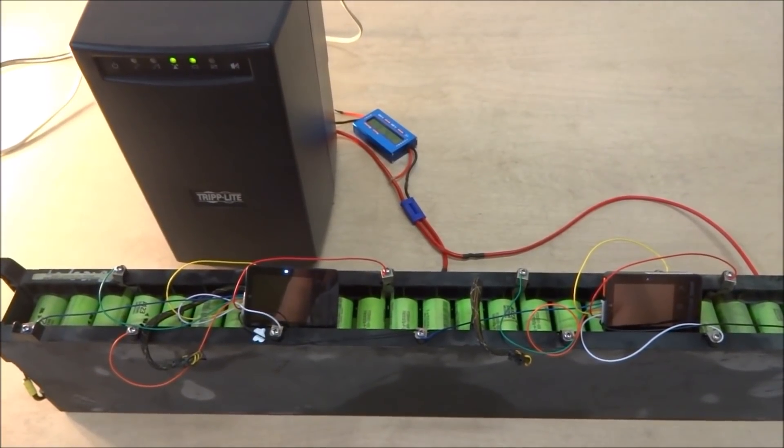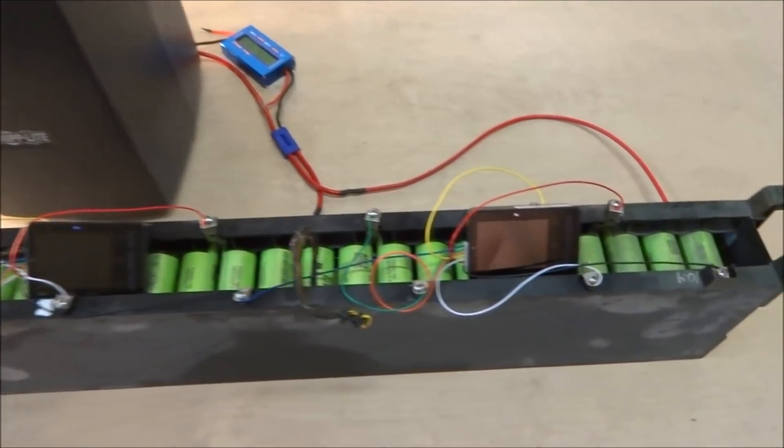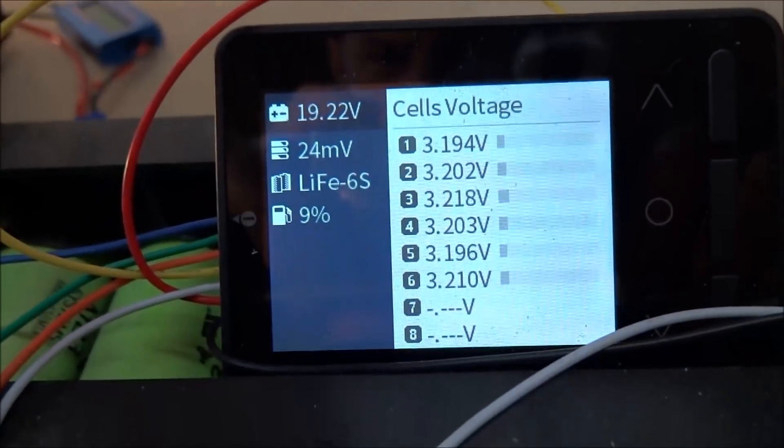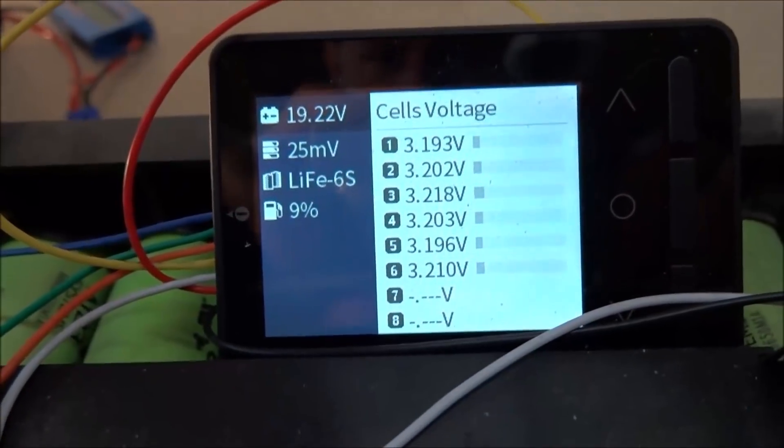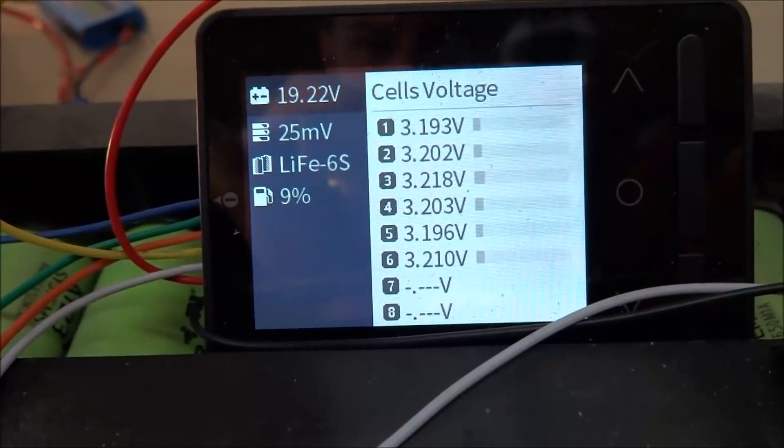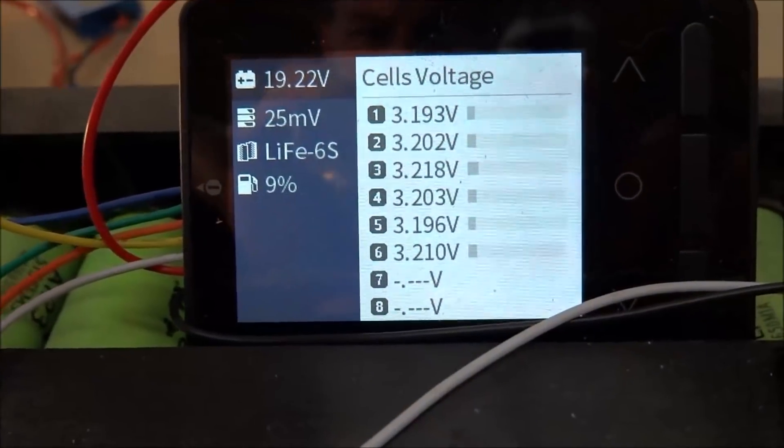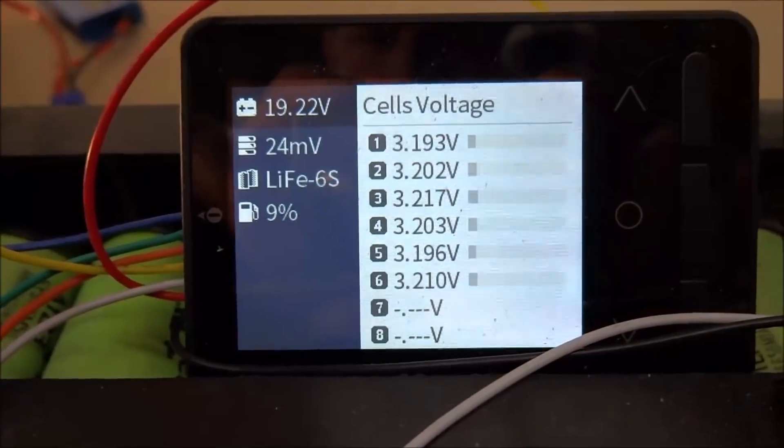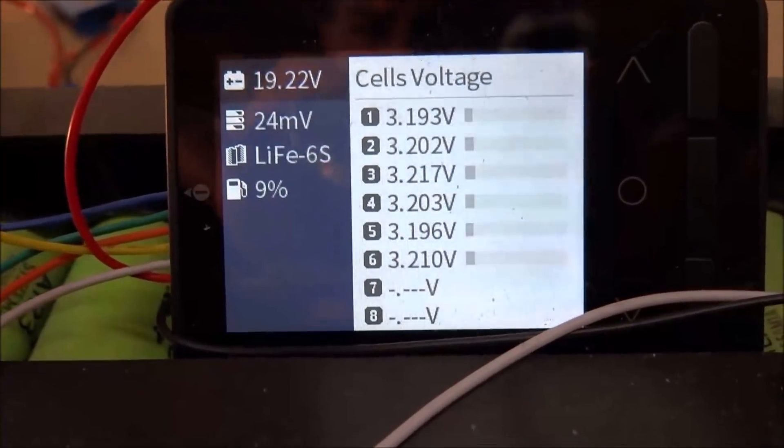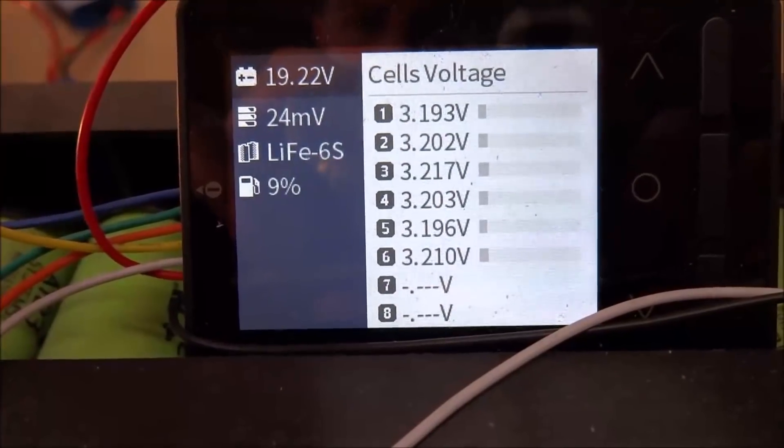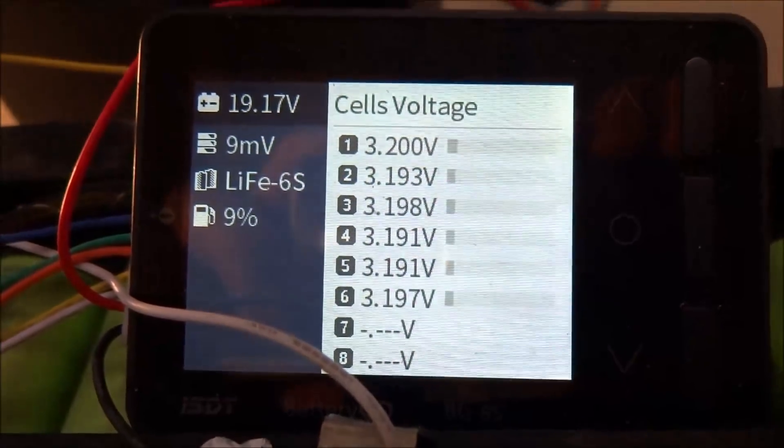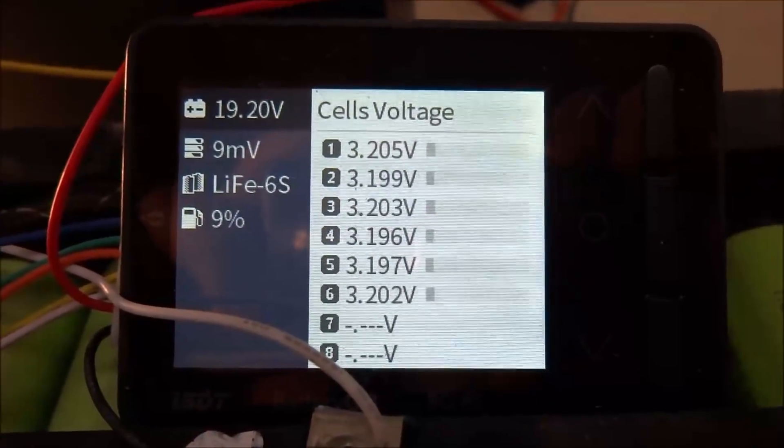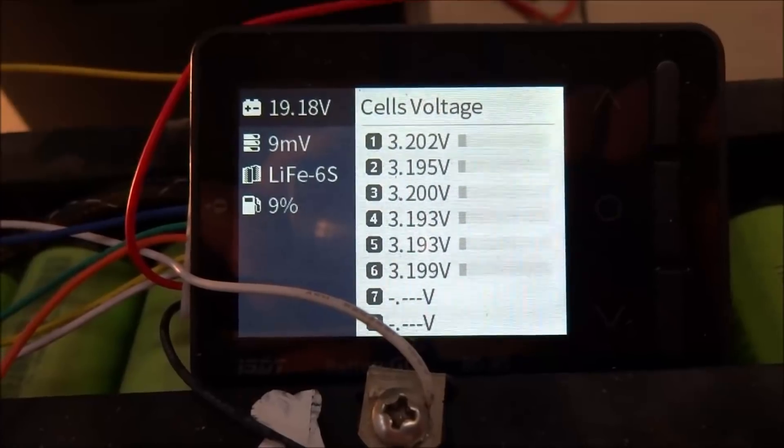The UPS has now been running for about half an hour, so let's see the state of voltage. As you can see, it's indicating 9% state of charge, however that's not accurate when it's on a load. The variance has been reduced now to only 24 millivolts, and on this one that's even better. I only have 9 millivolts difference.